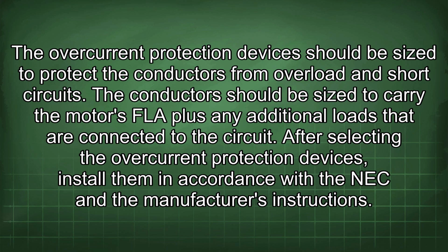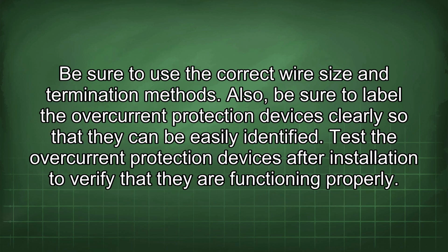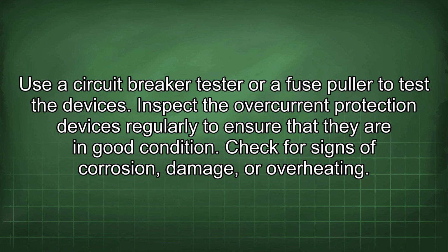After selecting the overcurrent protection devices, install them in accordance with the NEC and the manufacturer's instructions. Be sure to use the correct wire size and termination methods. Also, be sure to label the overcurrent protection devices clearly so that they can be easily identified. Test the overcurrent protection devices after installation to verify that they are functioning properly. Use a circuit breaker tester or a fuse puller to test the devices.